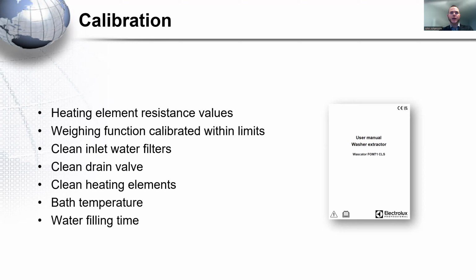A good and easy way to keep the heating elements clean and to avoid limestone buildup is to use citric acid, about 0.5 kilo, and run the highest temperature program in your machine with citric acid to keep them clean, and do this on a regular basis. The bath temperature should be measured.